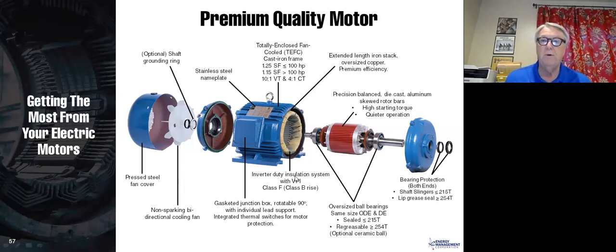This is inverter duty. We probably are not going to be able to get into that this time due to time. This presentation we're going through is actually a 6-hour training class. So if you want a really good quality motor, what you want to get is a stainless steel nameplate, get a motor with service factor, make it premium efficiency, get precision balanced, aluminum skewed rotor bars, get bearing protection, use oversized bearings, and use a TEFC motor with a cast iron frame. And make sure, because it's TEFC, the air doesn't go through the motor, it goes over the outside.